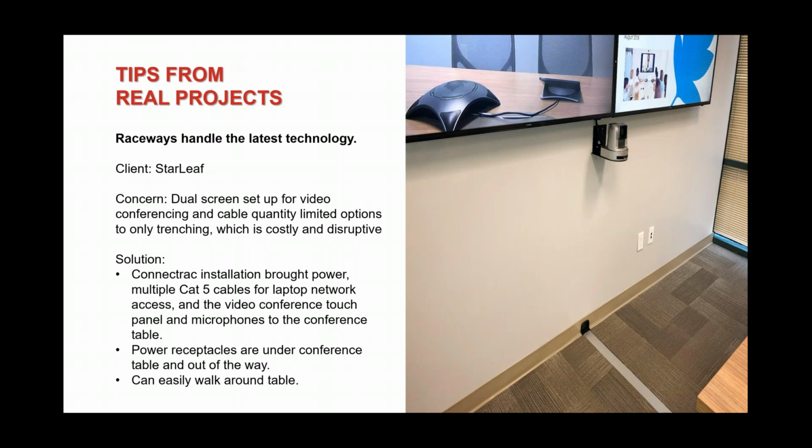We had a client, and it wasn't StarLeaf, but it was another client who has the latest and greatest, most expensive Cisco systems and tons of conference rooms. And they said, we need to test this to make sure there is no interference. I said, please do. We would love to know. They tested it, their AV IT team, and said there is no interference. So they ran the cables right next to that shielded power that we have. So you can do that.